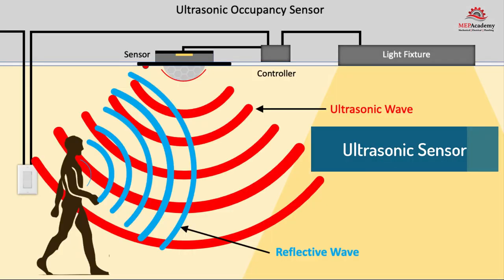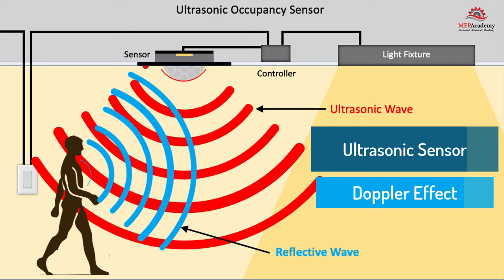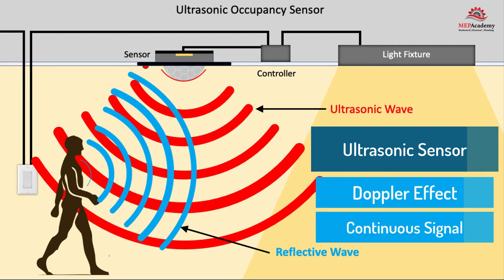An ultrasonic sensor emits high frequency sound waves that bounce around the room and objects but are not heard by humans. The sensor picks up any movement by noticing a change in sound wave frequency. This is based on the Doppler effect — the change in frequency of a wave in relation to an observer moving relative to the wave source. Since the ultrasonic sensor sends out a continuous signal, its electrical power consumption will be higher than the wireless passive infrared sensor.